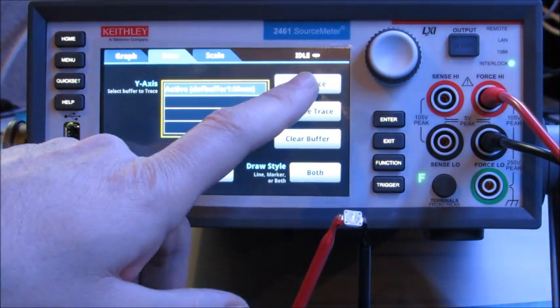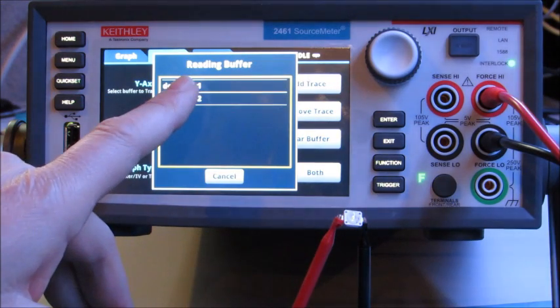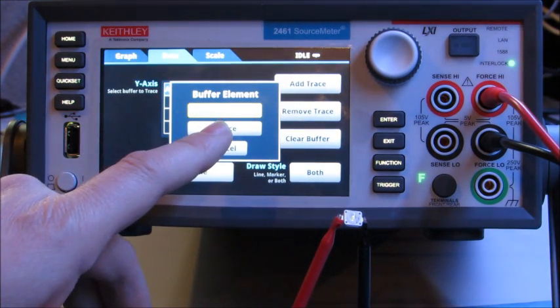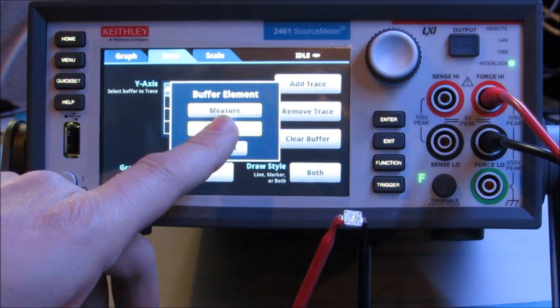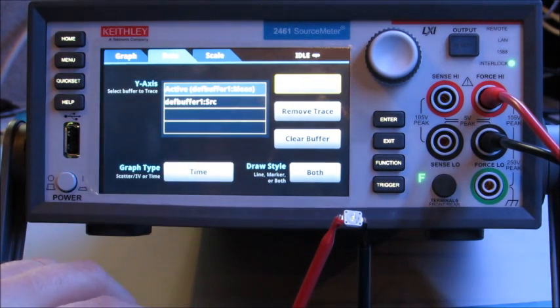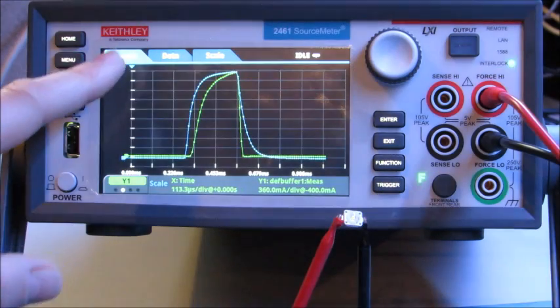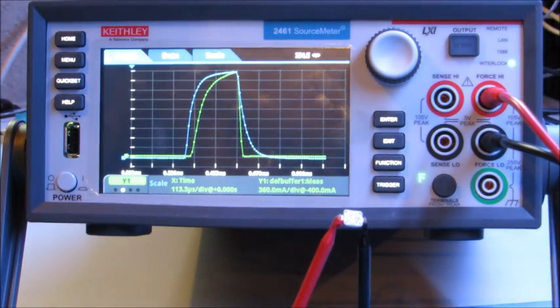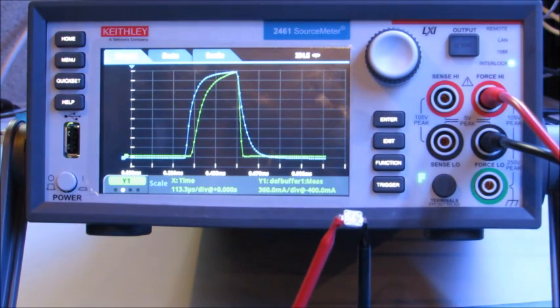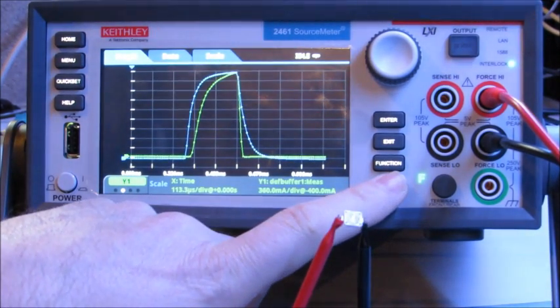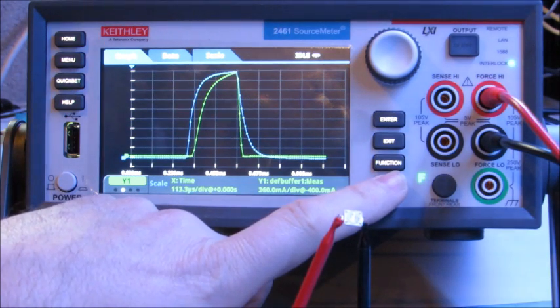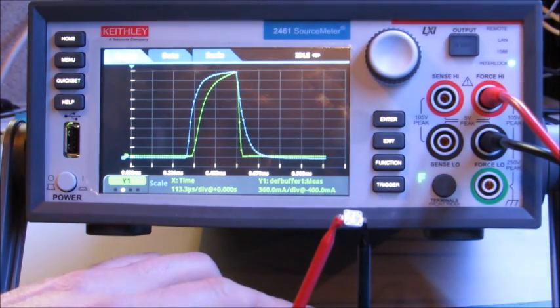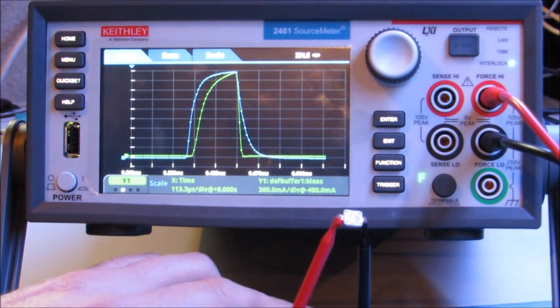So let's add a trace. Def buffer one is where I'm actually collecting my data. And I'm going to hit buffer element source so I can view the source value at the same time. I hit graph. And now you can see a blue trace that is the measured readback of the voltage pulse. So now if I hit my trigger button, now I can capture both pieces of information. The blue being the voltage pulse and the green being the measured current pulse.